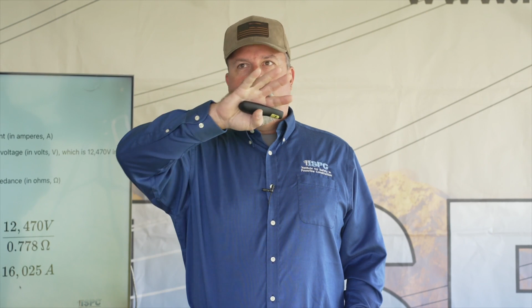But the thing that we need to understand is we don't know when a fault's going to happen. We don't know when somebody's going to accidentally re-energize a circuit, right? It's hard to determine what level of induction or induced voltage you may have in your grounded circuit when you're working. We don't have the ability to figure out or determine when all these things are going to happen, right? That's why they're incidents or accidents, right? And so the only thing we can do as workers is every single time build our grounding systems, do our connections and our conductors the right way every time. It's the only way we can hopefully prevent ourselves from being part of that.